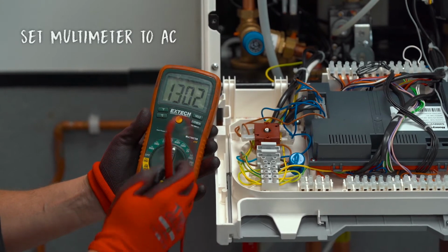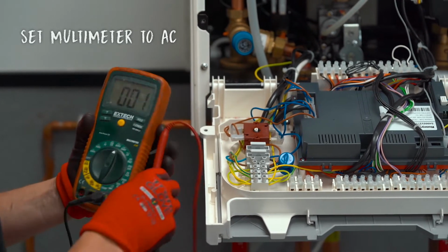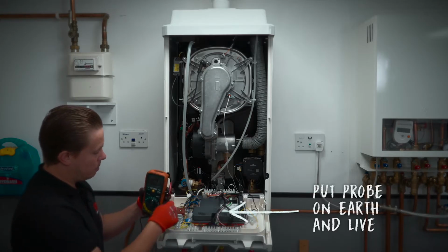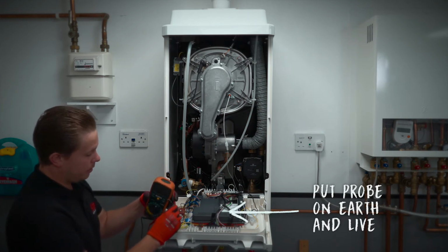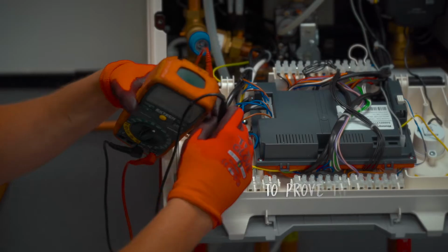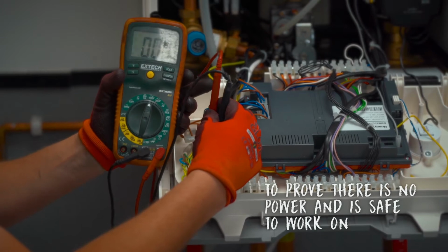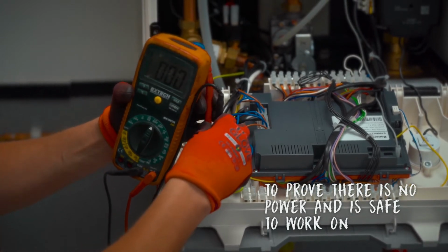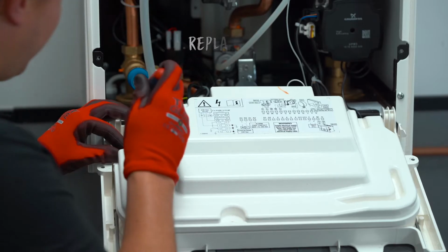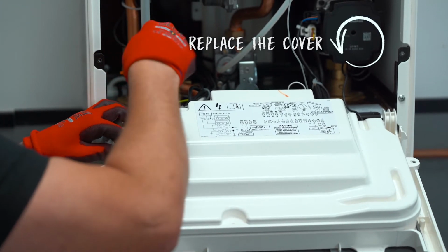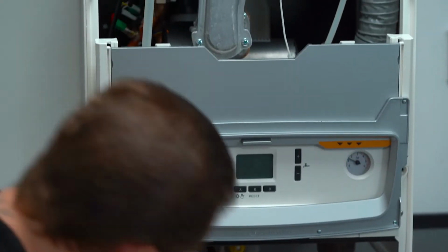Using a multimeter, select volts AC. Place your multimeter probes on connections live to earth, neutral to earth and live to neutral. After this has been carried out, you can confirm that safe isolation has been achieved. The appliance is now ready to be worked on, and the control panel cover can be replaced.